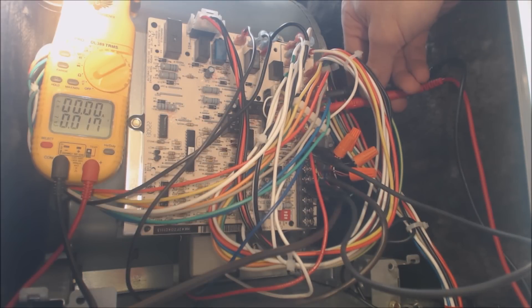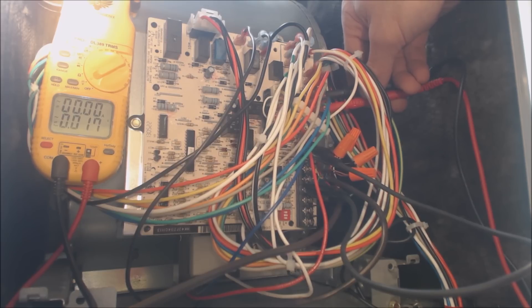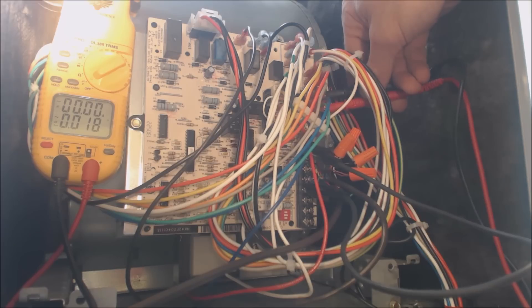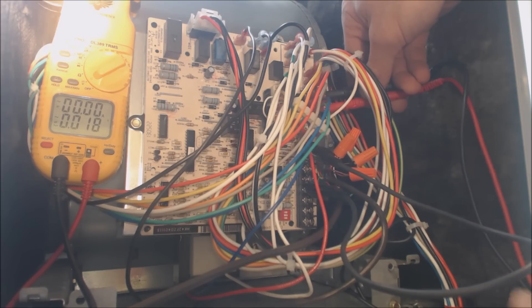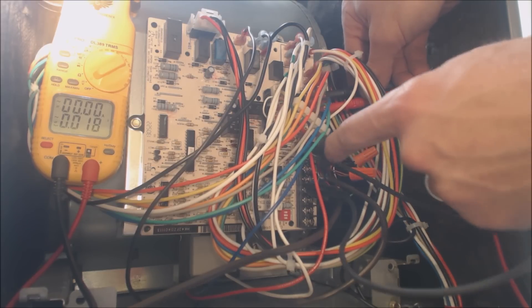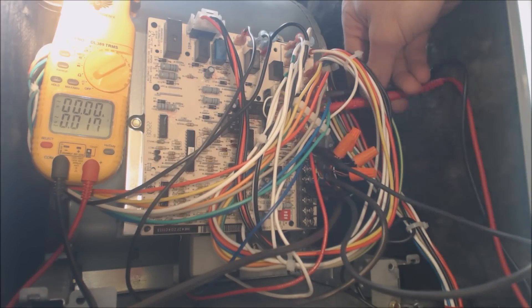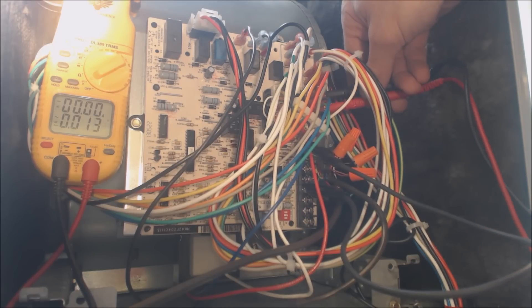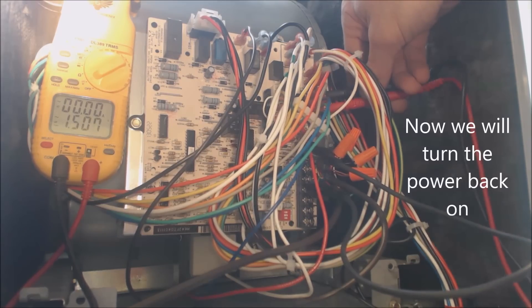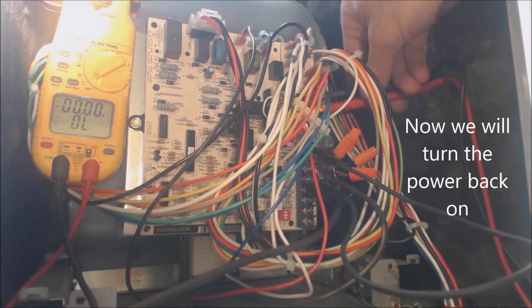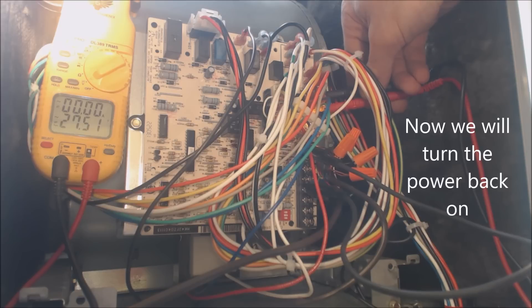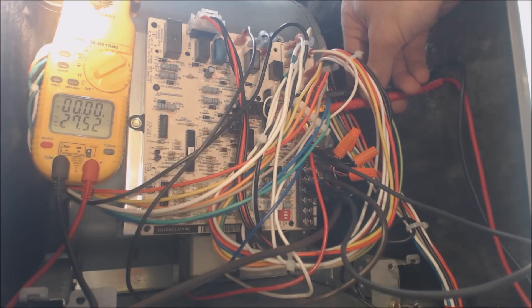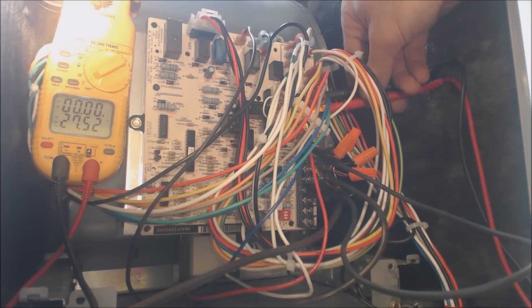So presently I have my probes on the green, which is common, and the gray, which is going to be the 24 volt hot going to the blower motor. We have our alligator clips connected to the green and connected to the red. So now we're going to go ahead and read voltage. And we have 27 volts going to the blower motor, and we should hear the blower motor start here in a second.